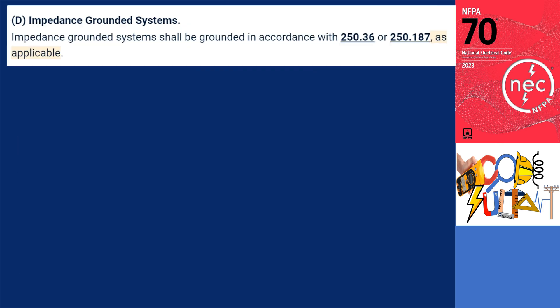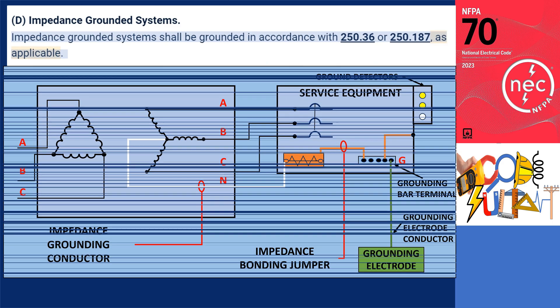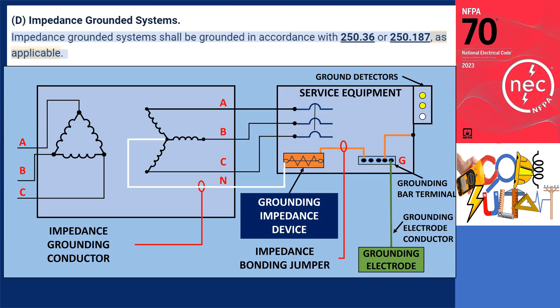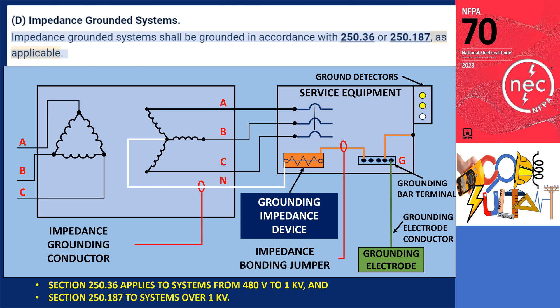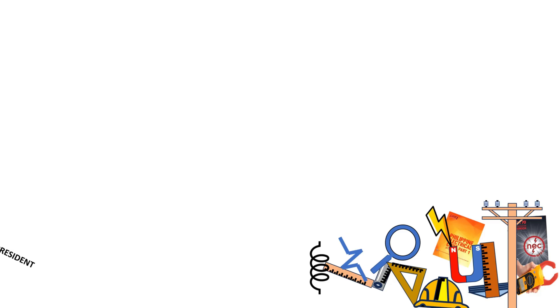Section 250.20D — Impedance Grounded Neutral Systems. Impedance Grounded Neutral Systems shall be grounded in accordance with section 250.36 or section 250.187. These systems are grounded, but through an impedance device rather than through a solid connection. Section 250.36 applies to systems from 480 volts to 1 kilovolt, and section 250.187 applies to systems over 1 kilovolt. Thank you all for watching.